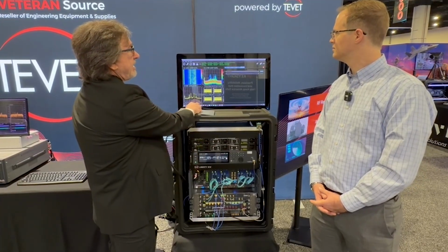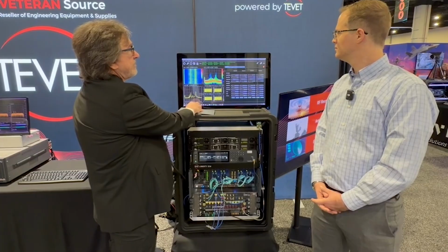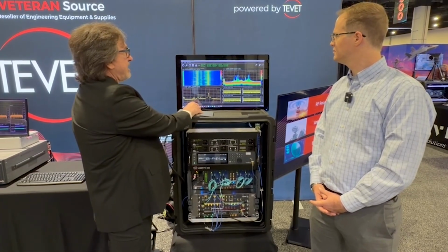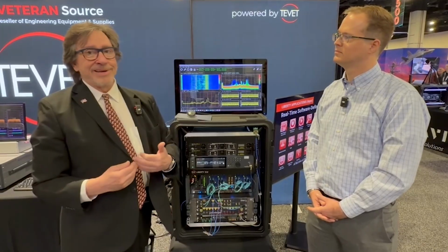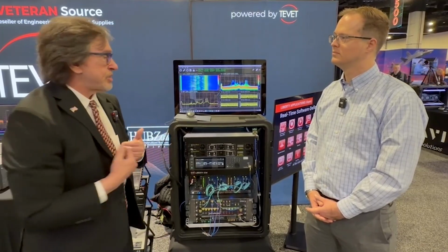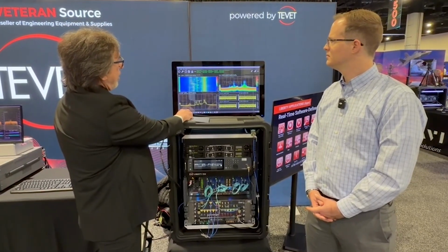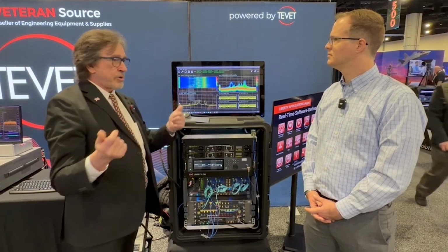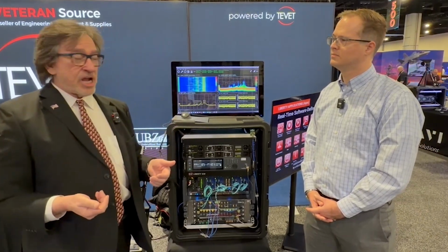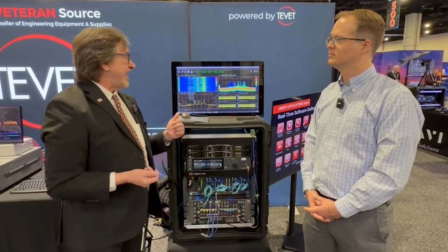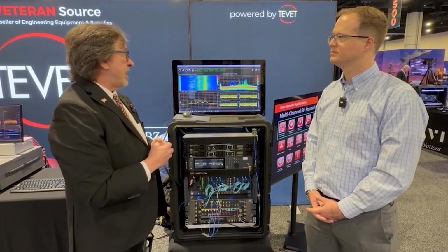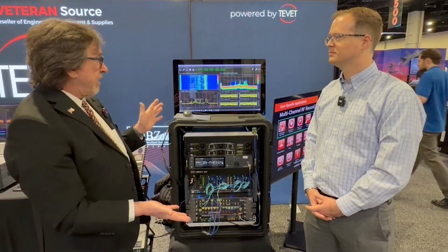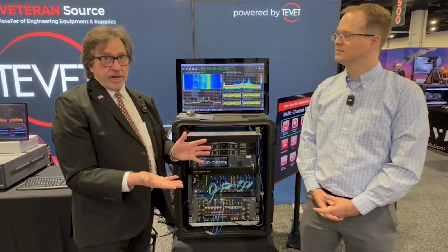If I then come out of that and go back to the instrument here, from a record standpoint, it is straightforward. We've chosen just a software trigger. That's the ARM function here. Boom, I just recorded data. We have it set up in snapshot mode, and so it just grabbed data and then displayed that data. So that is an overview of our multi-channel real-time spectrum analyzer.